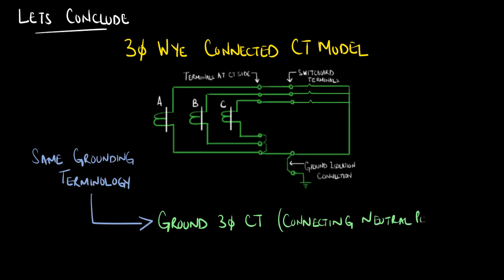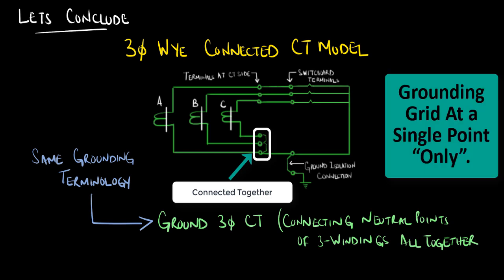We will be discussing this concept in more detail in a later series. We will now sum up the discussion by drawing a three-phase Y connected current transformer model. Following the same grounding terminology, we ground a three-phase CT model by connecting the neutral points of the three windings together, which is followed by connecting them to the grounding grid at a single point only.